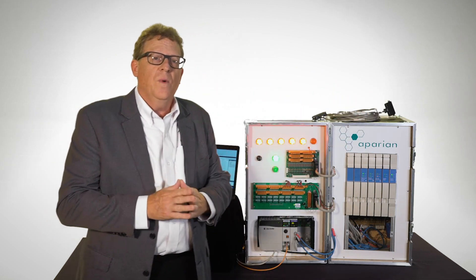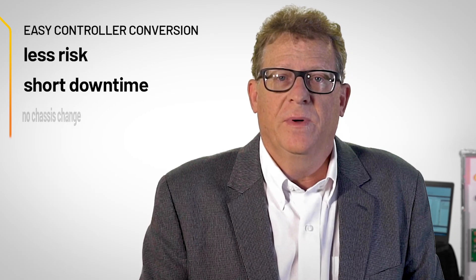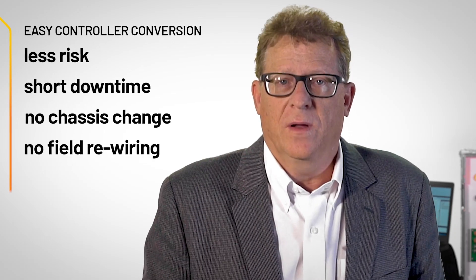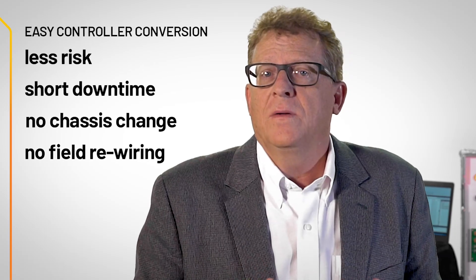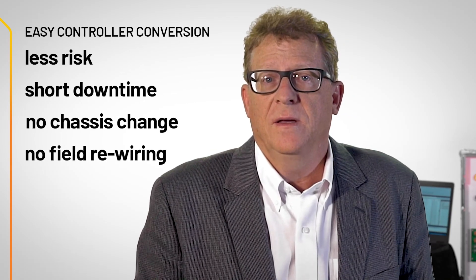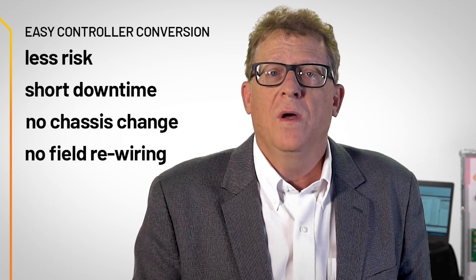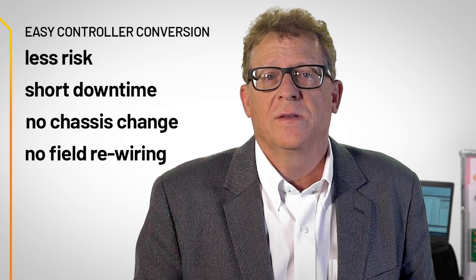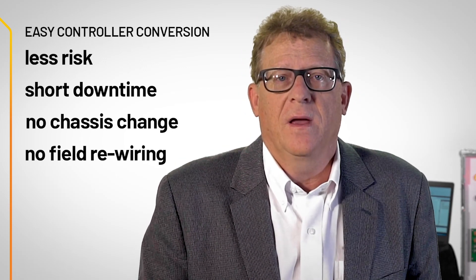I'd like to mention one more important solution. Rockwell has the capability to convert the C200 controllers directly to ControlLogix. This is a very simple and extremely fast hardware cut over since the C200 chassis is maintained and all new ControlLogix controller and I/O cards are inserted in the chassis. This is a very low risk conversion since it requires no field rewiring to the terminations and they're simply just reconnected to the equivalent 1756IO cards.